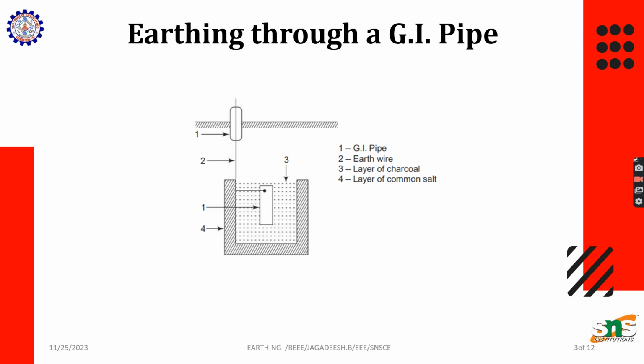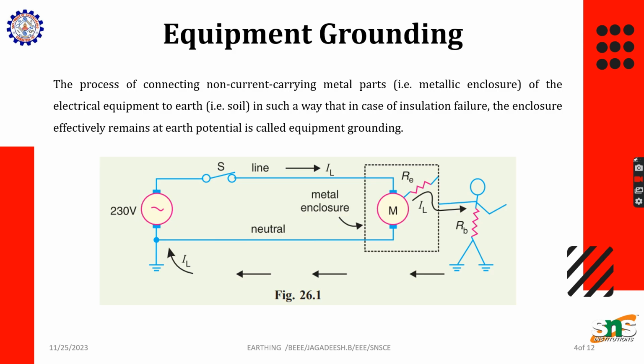All right. So let me take you into the two different kinds of earthing. One is equipment grounding, also called earthing. As I said, the non-current carrying metal part can be connected. That is exactly called equipment grounding. It is the process of connecting the non-current carrying metal part of any equipment to the earth or ground, to protect against insulation failure.